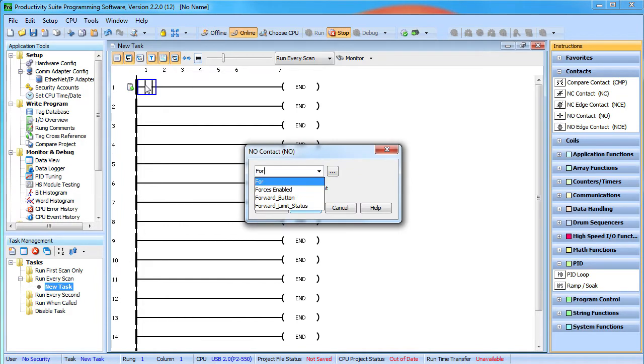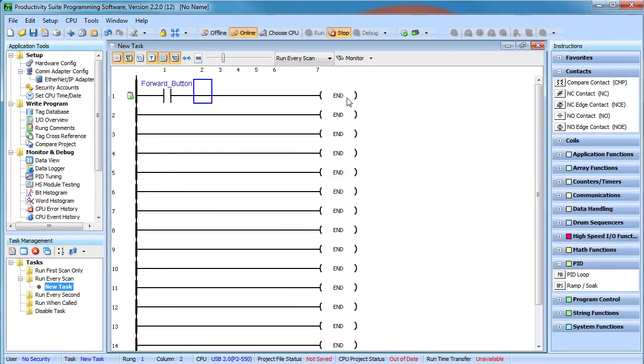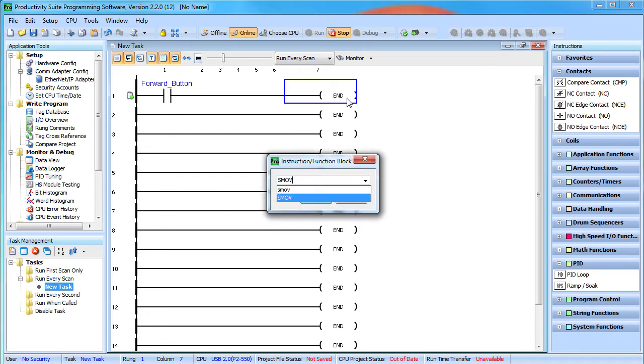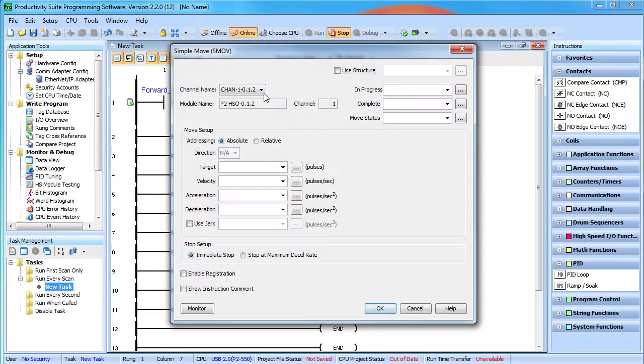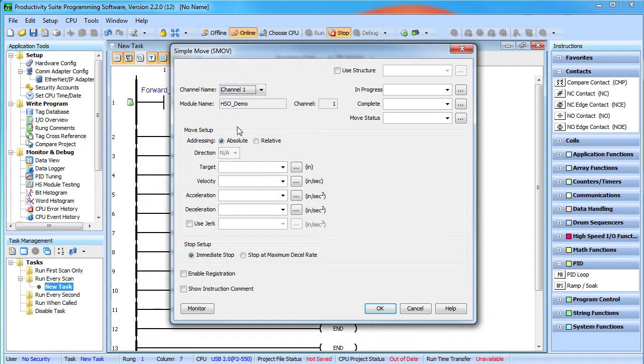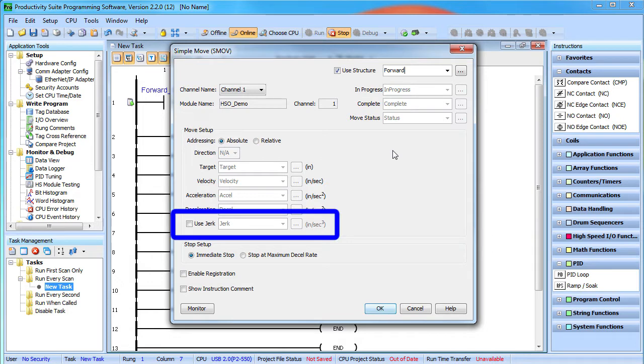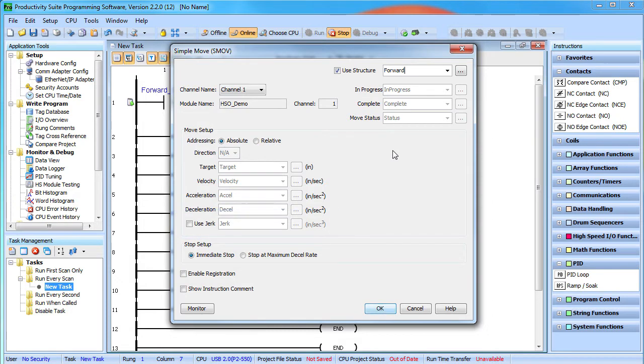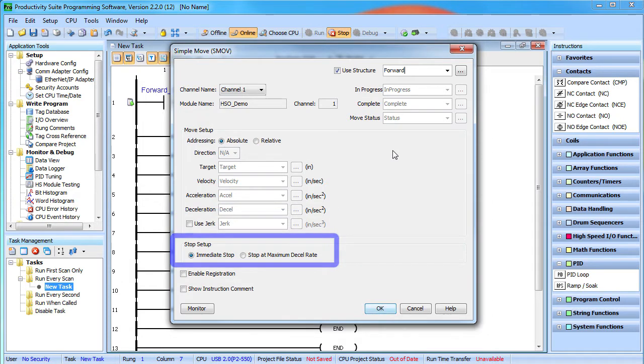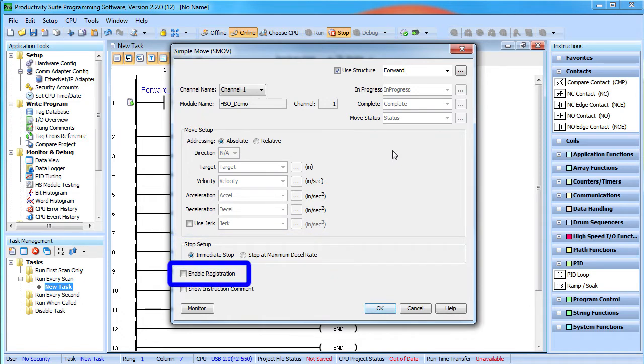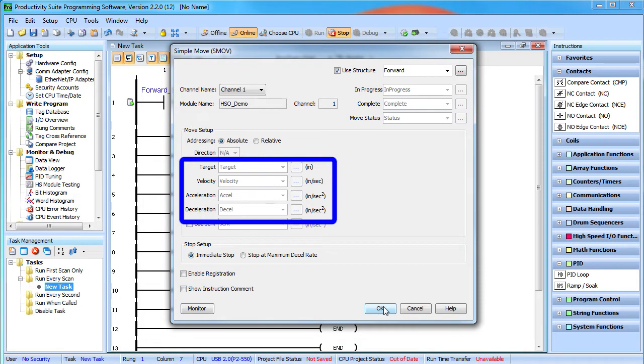We'll use the forward button that was defined in the hardware configuration to enable a simple move command. We want to use the channel that was also defined in that hardware configuration. Let's use absolute addressing and rather than filling in all these blanks I'm simply going to say I want to use a structure and call that structure forward. We'll cover jerk in a separate video. We want the carriage to stop immediately if there is an error or if we terminate the move early. We'll cover registration in a separate video. We'll fill in the values for position and velocity and acceleration in the data view.